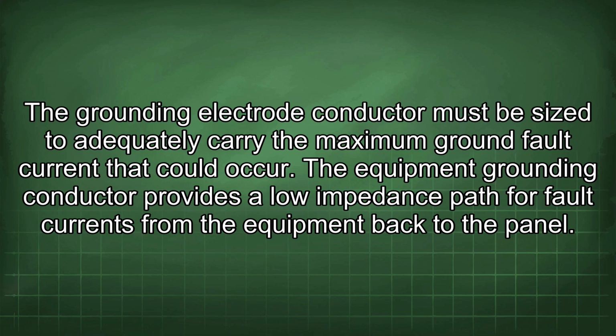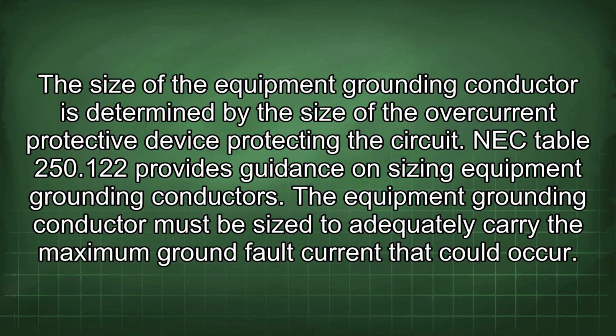The equipment grounding conductor provides a low impedance path for fault currents from the equipment back to the panel. The size of the equipment grounding conductor is determined by the size of the overcurrent protective device protecting the circuit. NEC Table 250.122 provides guidance on sizing equipment grounding conductors. The equipment grounding conductor must be sized to adequately carry the maximum ground fault current that could occur.